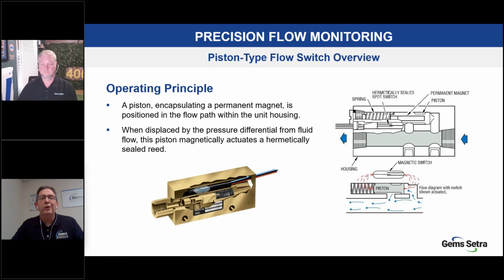So much easier to interpret on a reed switch device. The makeup is a reed switch, so it's a single pole double throw contact. There's a piston with a magnet embedded and a spring. As liquid flow comes through, it pushes on that piston, and the spring tension and the piston diameter determine where the piston will be at certain flow rates and put the magnet in the position to actuate the switch. It changes from its no flow switch condition to flow condition. Where this is really important is, again, as I mentioned before, if you're at or above that set point and your critical flow rate for your application, the sensor is actuated and you're able to run. But if you want protection, let's say the coolant loop is gone, it's off, you don't want to run the equipment at that time. When that flow drops below the set point, the switch returns to its normal state and you're able to say, I've got a problem, there's no flow.